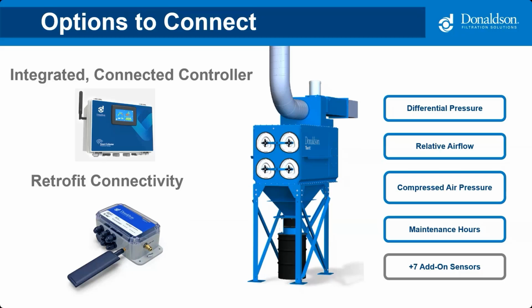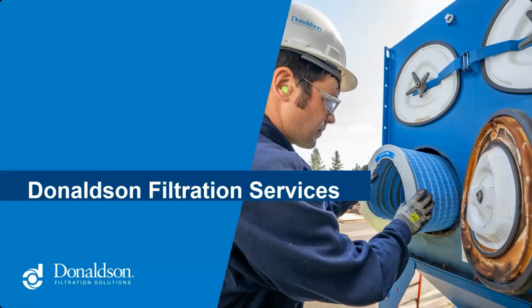We have a particulate monitor sensor that can go in the clean air duct and can let you know if you're starting to see leakage, or you've got leakage past a filter, maybe you have a damaged filter, or there's a leak somewhere else in the system. That's really handy for those of you that are dealing with air permits and you really have to make sure your collection system is really airtight. We also have speed sensors that can tell you if things like your rotary airlock or your screw conveyor is not spinning. If it's supposed to be spinning when the collector's on, which is true, this can trip an alarm that says, hey, collector's running, but your screw conveyor's not. So that's going to be a problem, right? You're going to have backup in the system. And there's several more as well that you can add on. You can view them all on our website and customize it how you see fit.